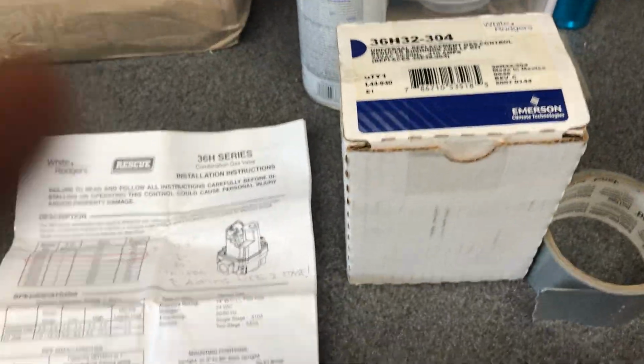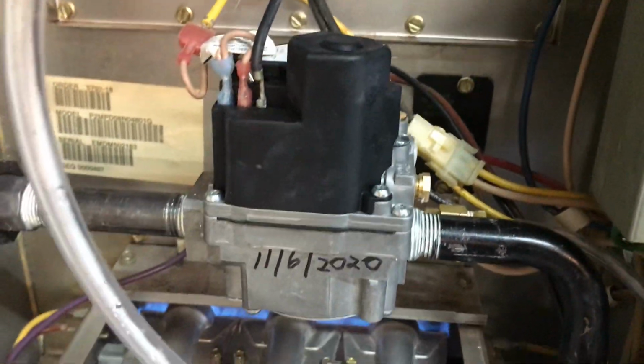So there's a dilemma. It's working okay, so I'm not going to complain about it too much. Sitting there running good at an inch and a half, which is 3 inches of water column. So I'll go ahead and write that on here, the adjusted 3 inches of water column on this date, whatever it is today. And I'm going to shut it all down.